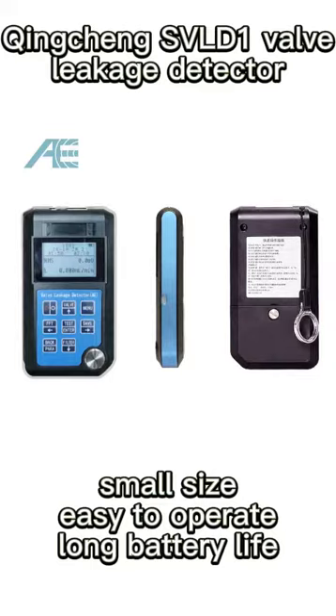The detector processes and calculates a certain sample length of acoustic signal to get three acoustic emission parameters: RMS, ASL, and power respectively, which can be the leakage reference values. In the meantime, by calibrating these AE parameters at certain known leakage rates, the detector can generate an acoustic emission parameters versus leakage rates calibration curve, so that it can give leakage reference rates during the tests.